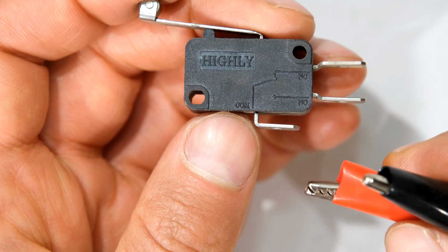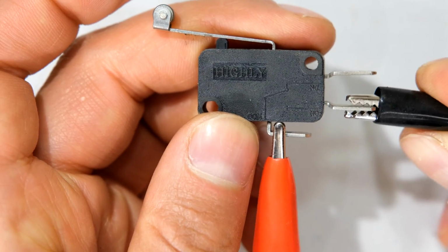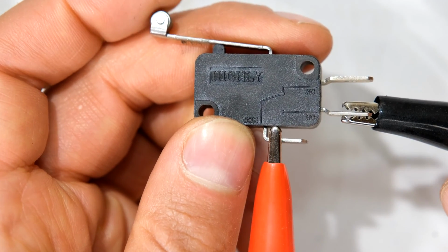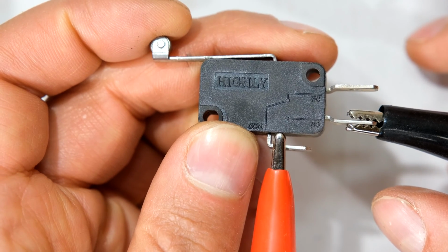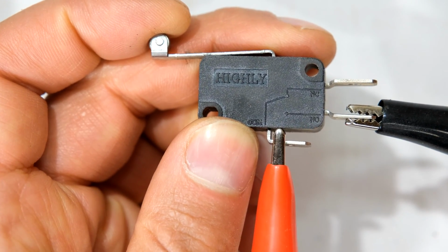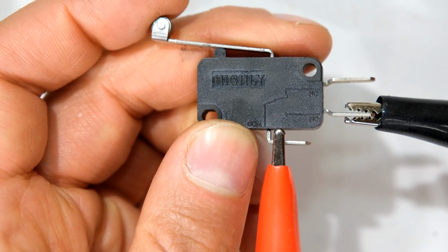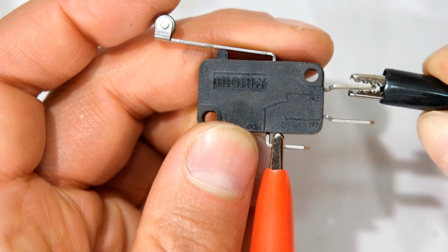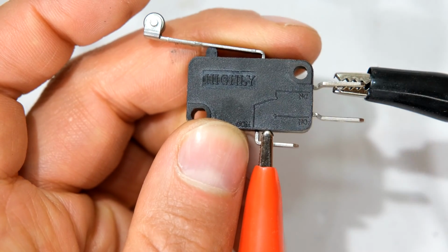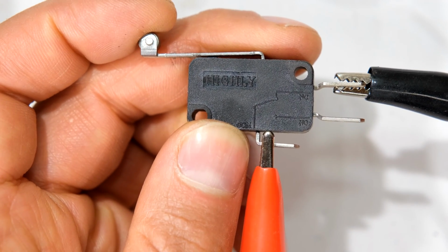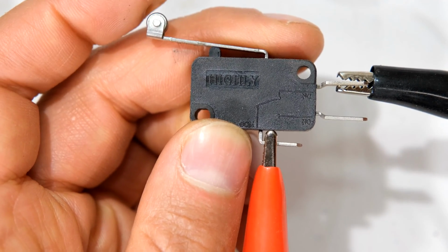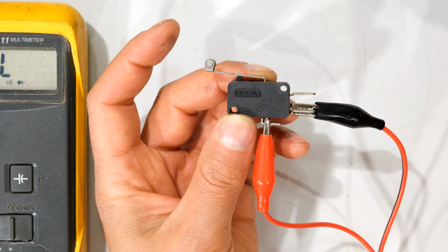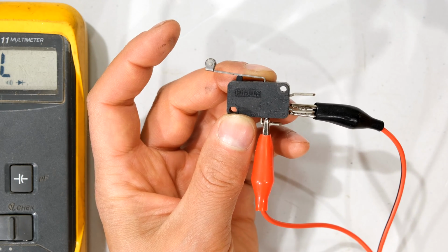So if I connect my meter to the common input and I connect my crocodile lead to the normally open, notice that the meter will only make the sound when I close the switch. How do you close a limit switch? I just depress that. Right, you should be able to hear the meter in the background. When I move this to the other side, it's closed already because it's normally closed. It'll open only when I depress the lever. It changes state while I'm depressing the lever, but when I release my pressure, it changes state again. That is why it is a momentary switch.